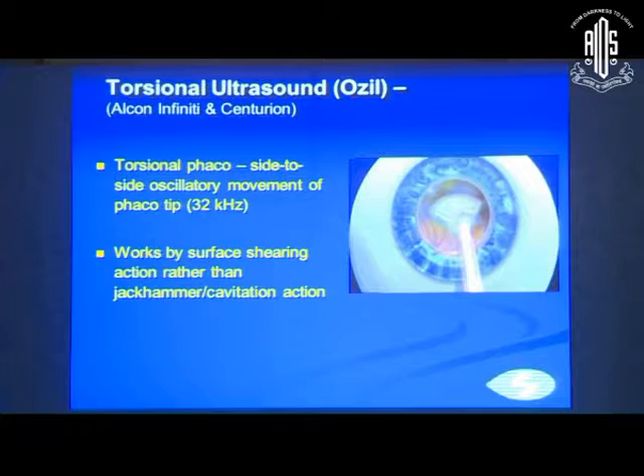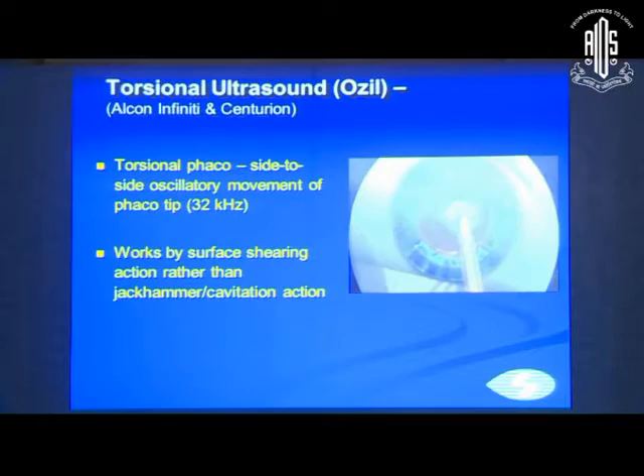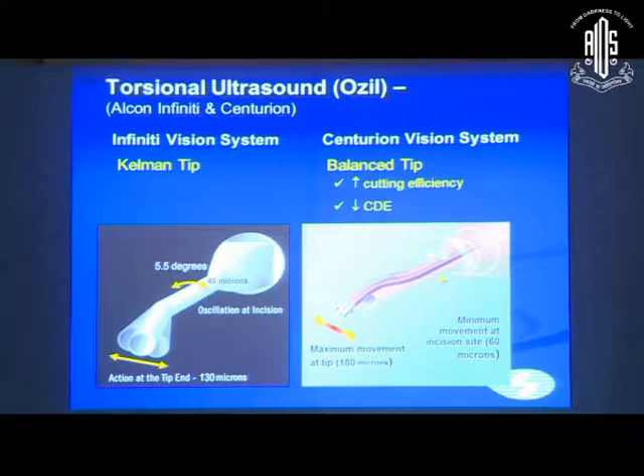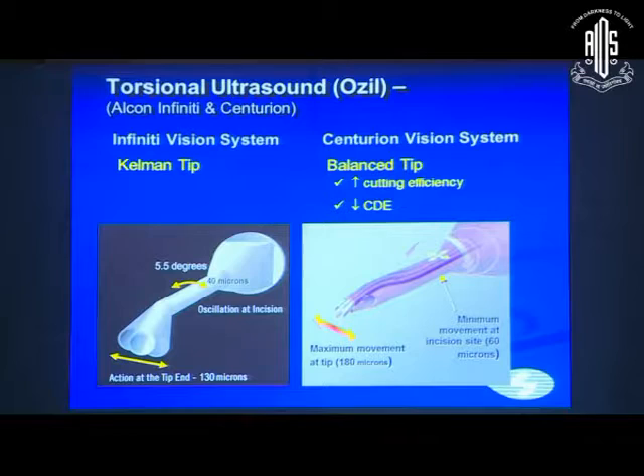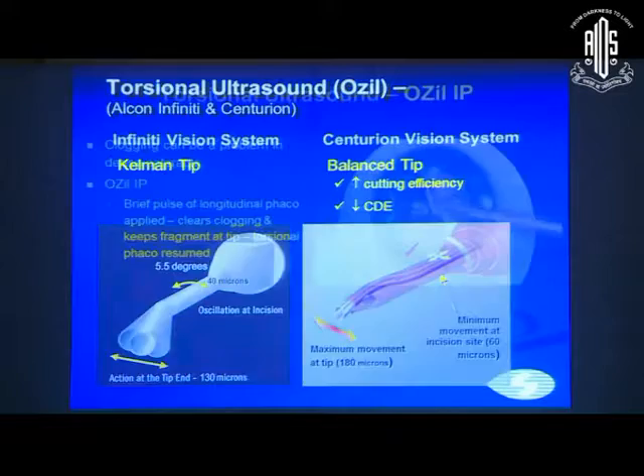Torsional phacoemulsification is a side-to-side oscillatory movement of the phaco tip, present in the Infiniti and Centurion machines. It works by surface shearing action rather than a jackhammer effect. The Centurion Vision System now has the balance tip, which increases cutting efficiency and decreases the CDE delivered inside the eye, due to its design achieving maximum movement of 180 microns at the tip compared to the earlier Kelman tip's 130 microns.